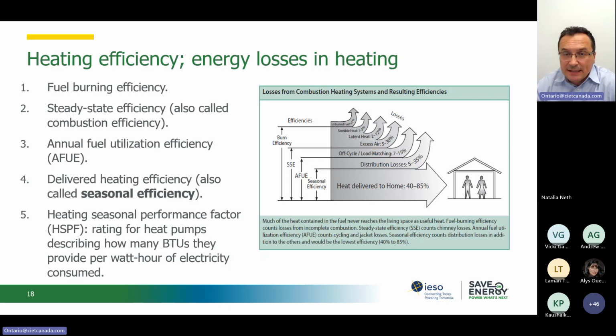And then this is basically the heat that we release from the chemical energy. And we can then look at the path of transferring this heat all the way to our space. But not all this heat, as we work with an indirect heating system, gets to be transferred towards the space. Some of it will be lost. And you see here in the first group of losses, we have sensible heat. This is because in the combustion reaction, we release some molecules of water that, if we don't condense them in a boiler that is not designed to condense the vapors from the flue gas, will be exhausted in the atmosphere and take with them the amount of energy we need, the latent heat of water that will be now present in the vapors.